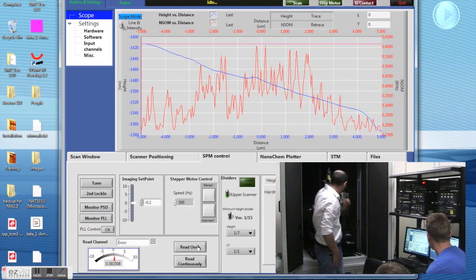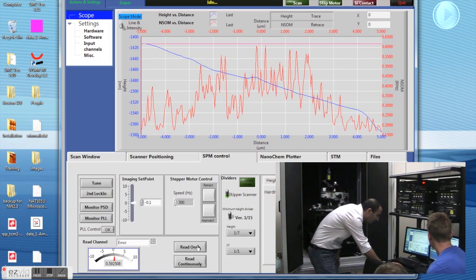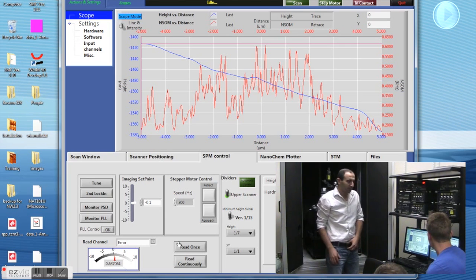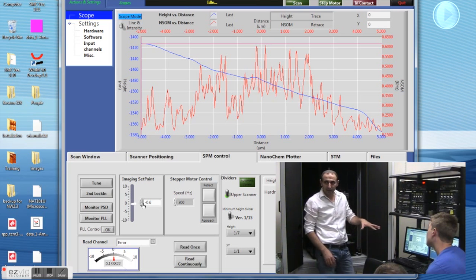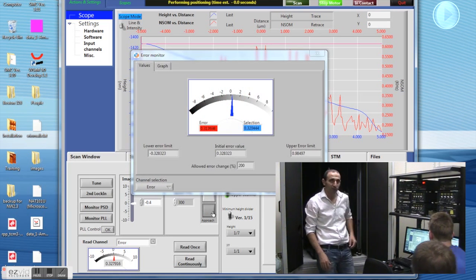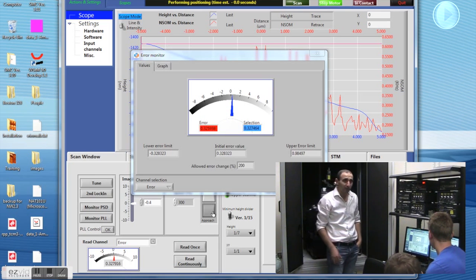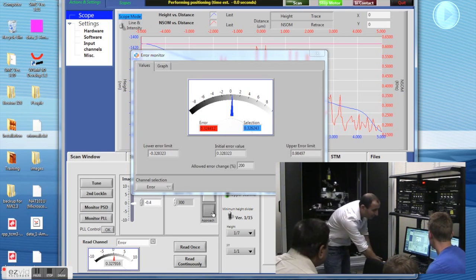Okay, so we switch down with the focus. You'll be able to see the sample. So this is the sample. This will be going down. So let's approach the tip. Not directly to the surface, slightly before, like a few microns above the surface, and then when we switch to the 50x objective, we'll have a better field of view, and we'll see the advantage of these exposed tips when they're touching the surface. So the tip is coming down now.